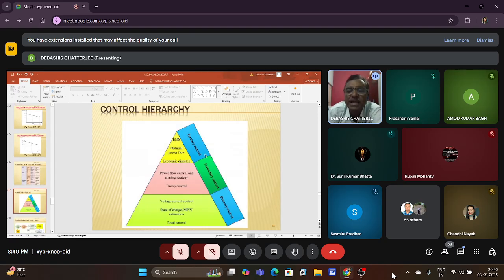And then there's another control hierarchy: you can have a primary controller, a secondary control, and a tertiary control. Primary control is at the base level - it covers voltage, current, state of charge, MPPT, load. Secondary is a little bit higher - we have droop, power flow control, and sharing strategy. And tertiary, again, is energy management system and optimal power flow - you are rising above this pyramid.